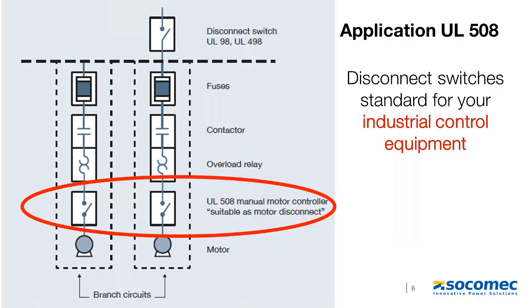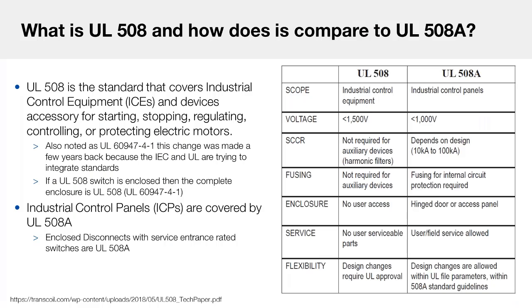The next standard is the UL508. So you can see in the same drawing from the previous slides where the UL508 switch would be implemented, just above that motor. First we have this UL508 standard, which is the standard that covers industrial control equipment and devices accessory for starting, stopping, regulating, controlling, or protecting electrical motors.